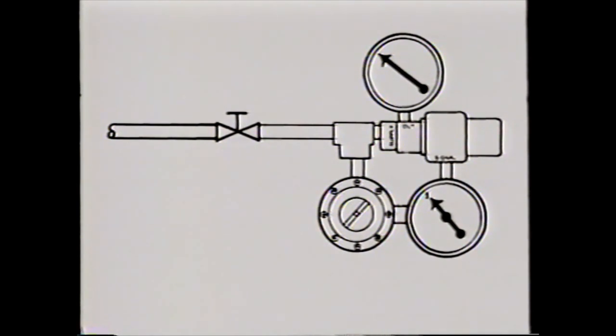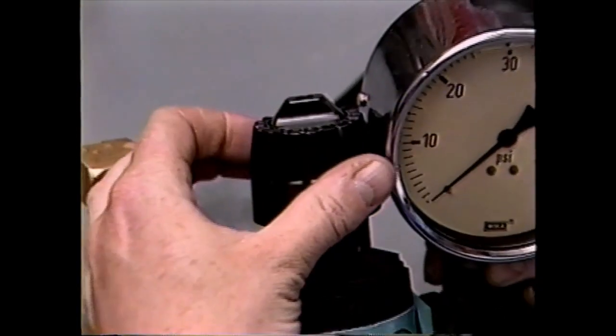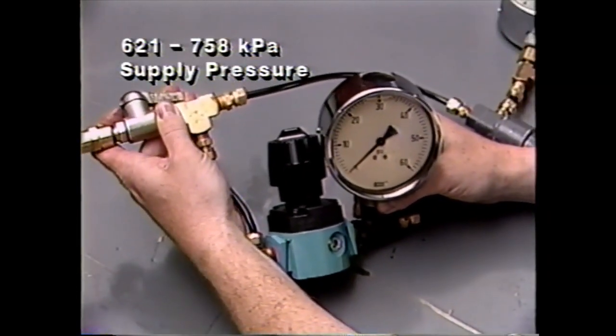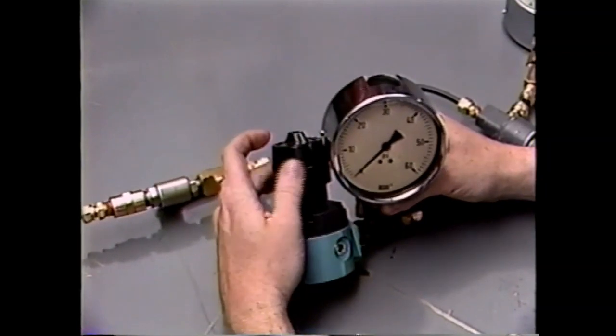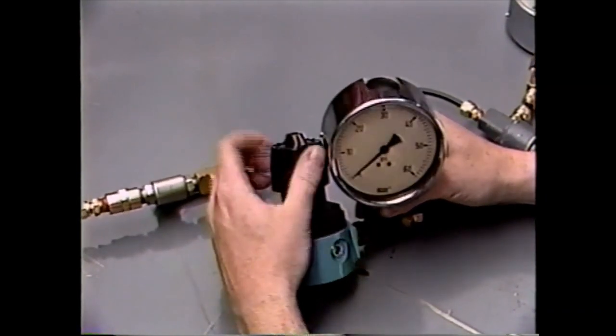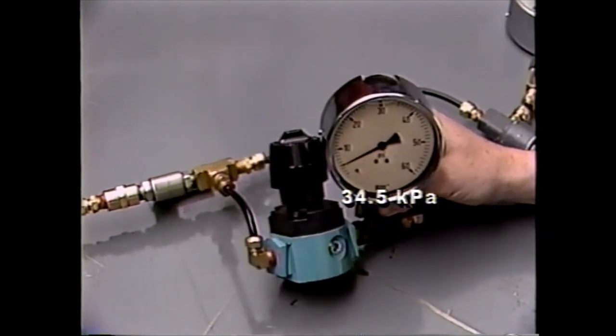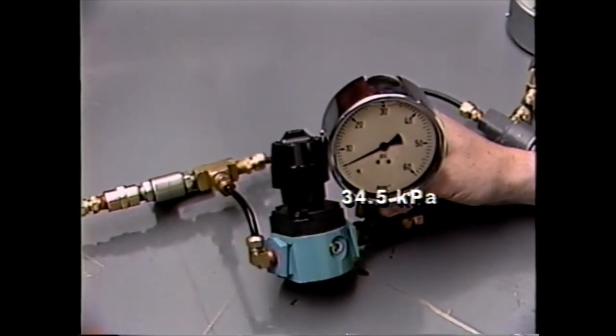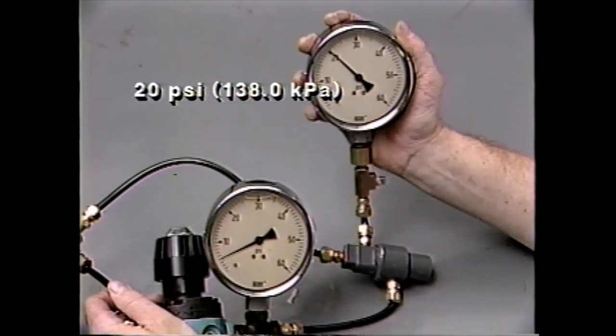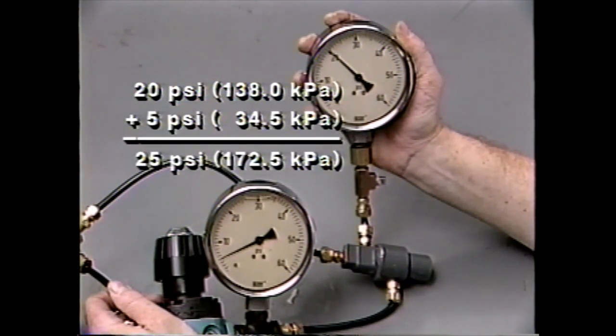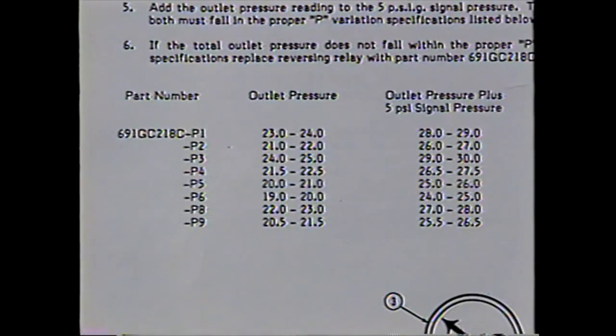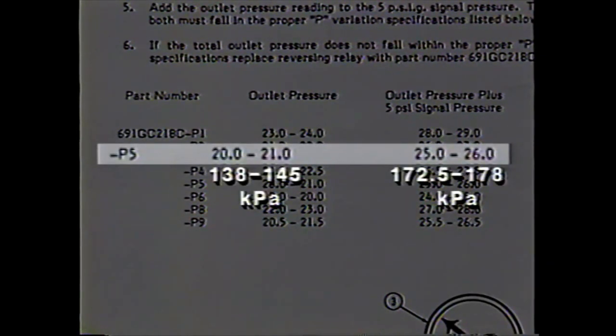To perform a test, do the following. Close the pressure regulator valve and slowly open the shutoff valve to apply 90 to 110 PSI air pressure to the supply port. Adjust the pressure regulator to apply 5 PSI pressure to the signal port. Now, note the pressure reading on the outlet port gauge and add the 5 PSI signal port pressure to the reading. Compare this reading to the specification listed for the part number of the relay you're testing. If the pressure doesn't fall within specs, replace the relay and test the relay output again.